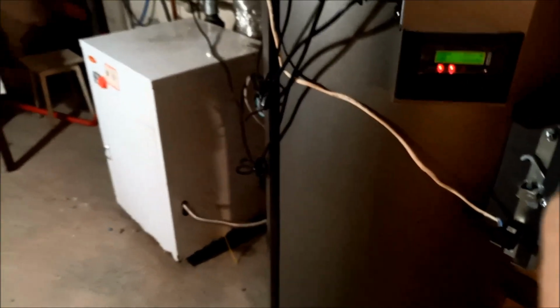We have a gas boiler and an electric boiler, and we were asked to add a solid fuel boiler to this system. But we have some problems: the maximum pressure this boiler can take is 1.8 bar, while this system runs on 2 bars or higher.